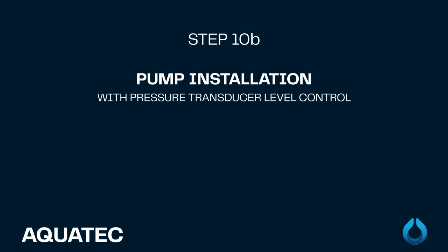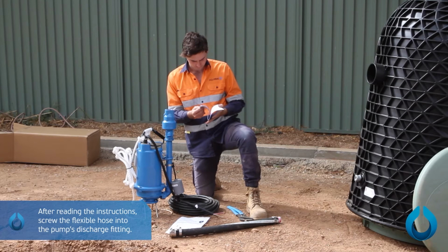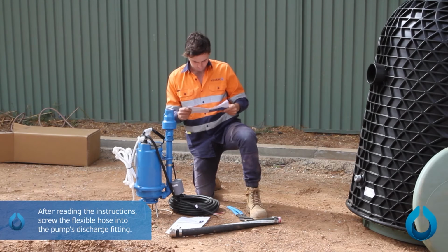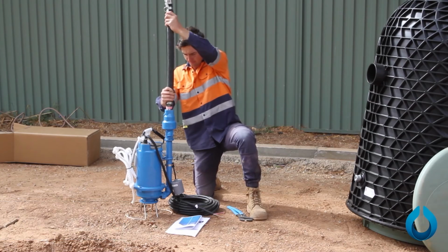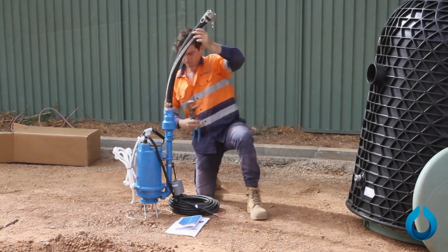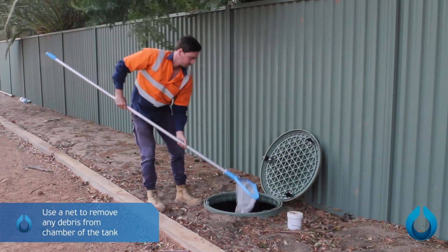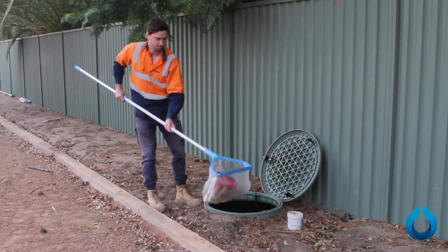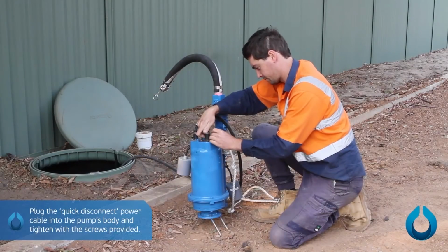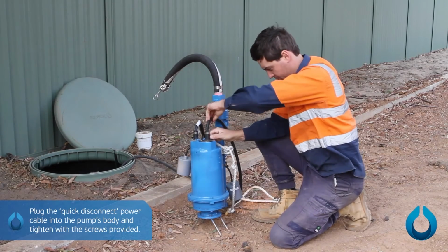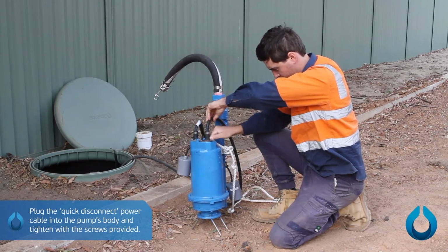Step 10B. Pressure transducer level control installation. After reading the instructions, screw the flexible hose into the pump's discharge fitting. Use a net to remove any debris from the chamber of the tank. Plug the quick disconnect power cable into the pump's body and tighten with the bolts provided.